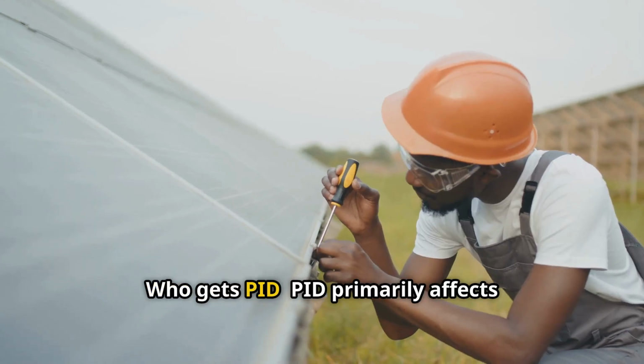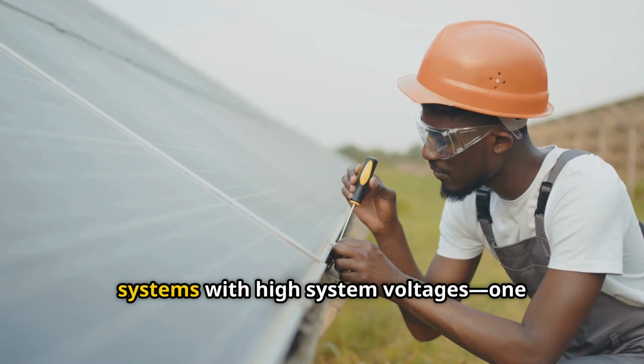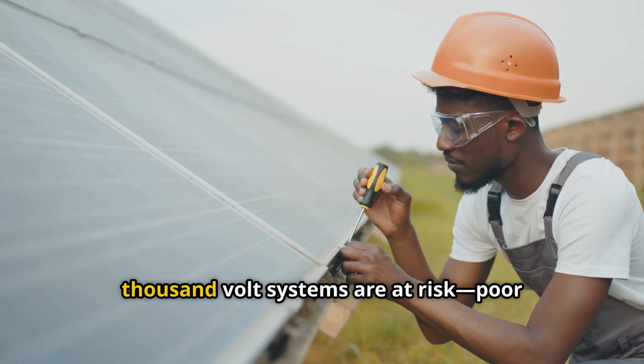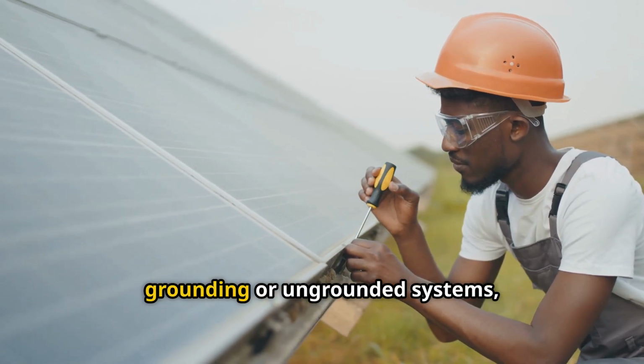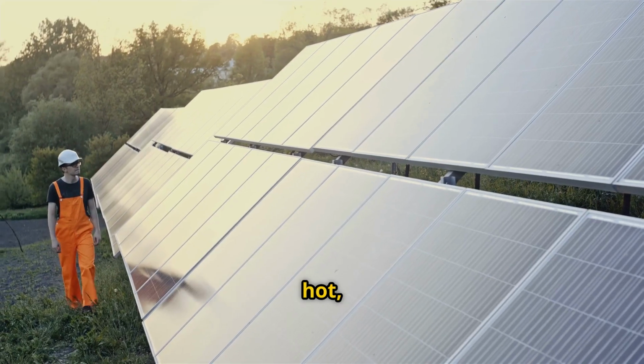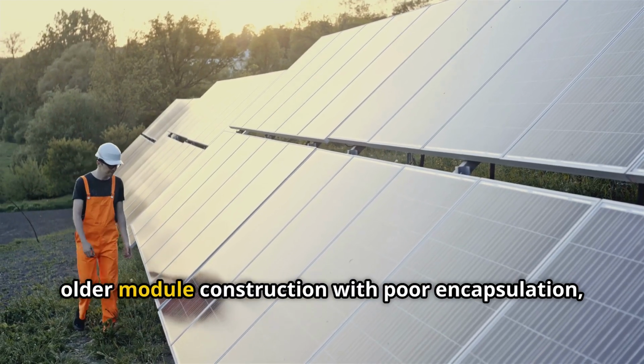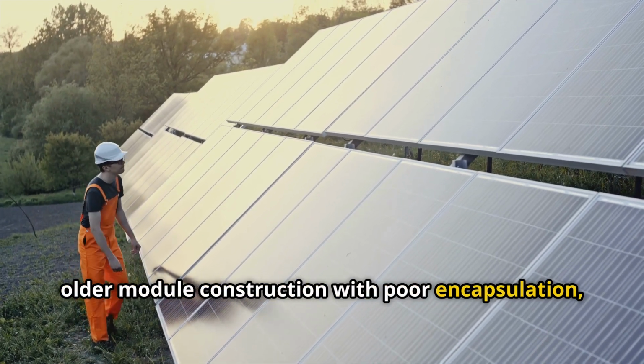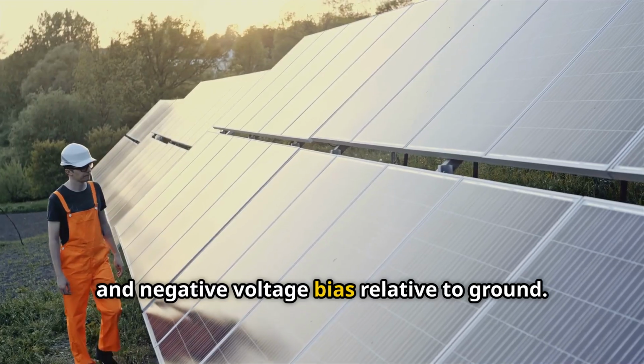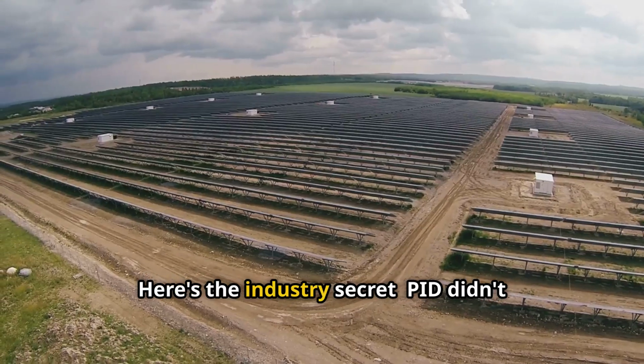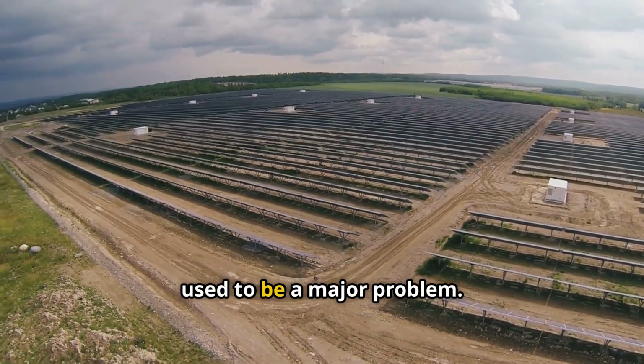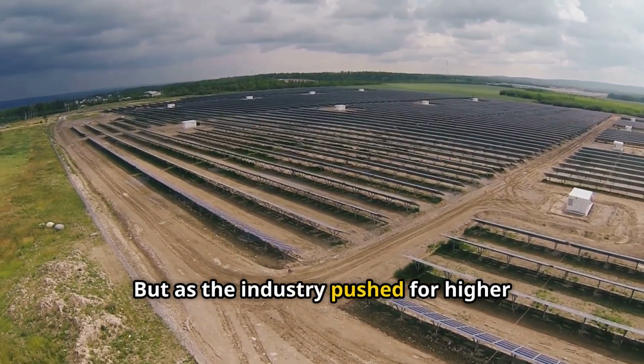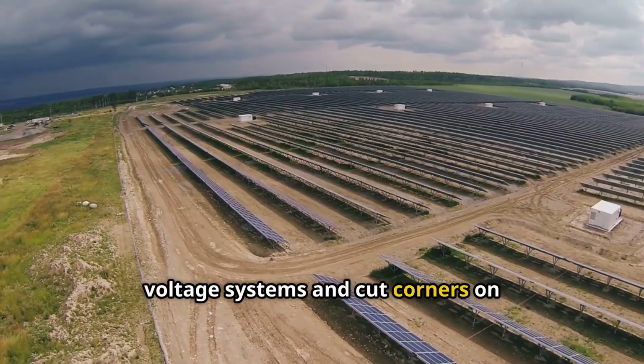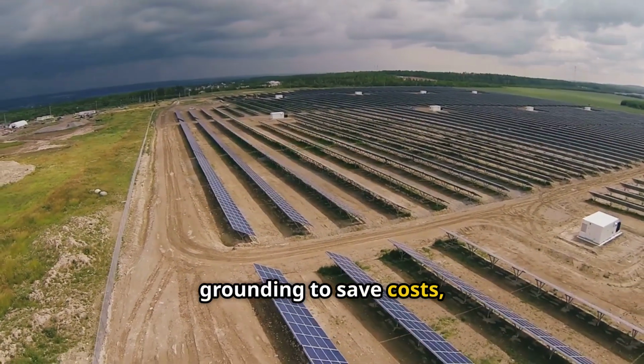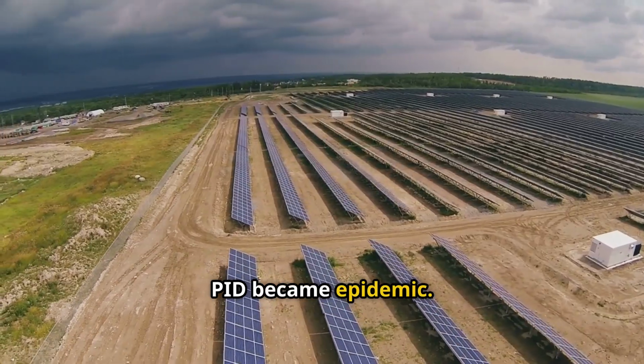Who gets PID? PID primarily affects systems with high system voltages. 1,000-volt systems are at risk. Poor grounding or ungrounded systems, hot, humid climates, older module construction with poor encapsulation, and negative voltage bias relative to ground. Here's the industry secret. PID didn't used to be a major problem, but as the industry pushed for higher voltage systems and cut corners on grounding to save costs, PID became epidemic.